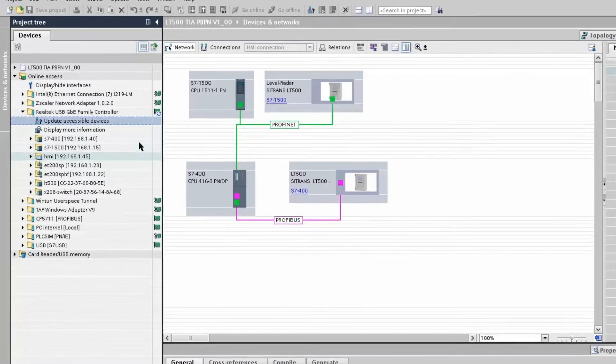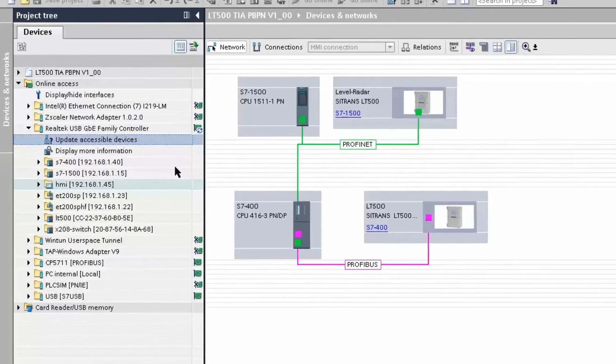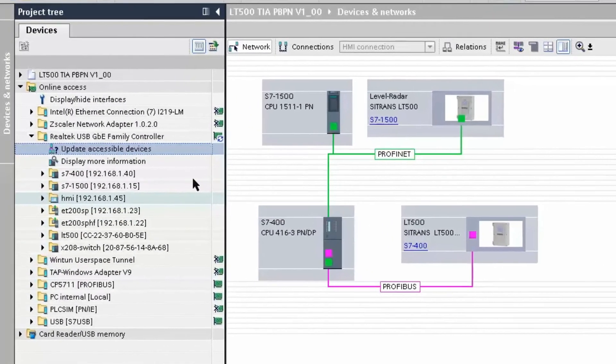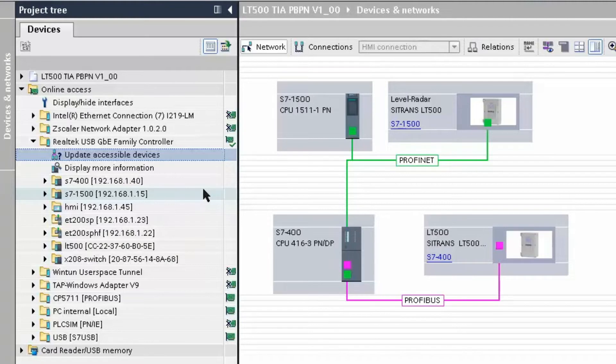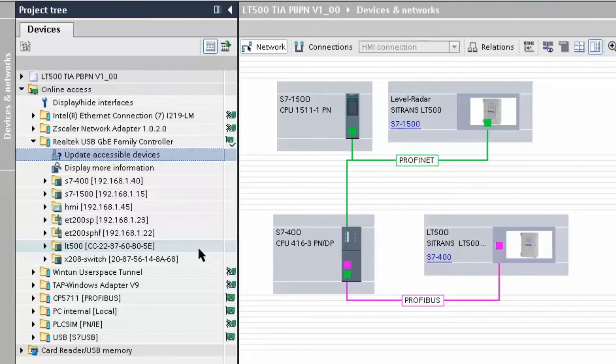If we update our accessible nodes once again, we now should see that the SITRANS LT500 has a device name. However, the SITRANS LT500 does not have an IP address, which means that it is not assigned to an IO controller yet. We will discuss further the IP address and device name later in this tutorial.